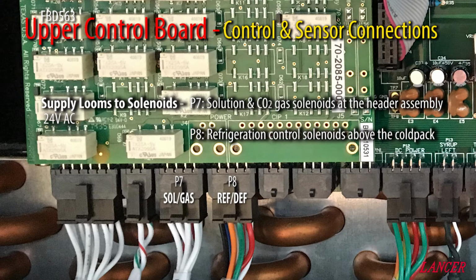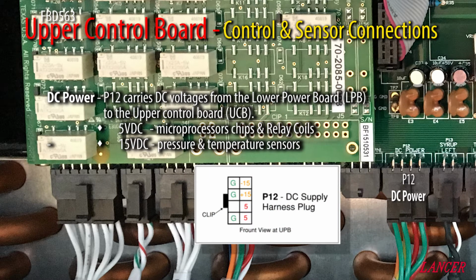These are the output control harnesses. P7 supplies the product, solution and gas solenoids. P8 supplies the refrigeration, pulse and hot gas solenoids. P12 is the DC supply cable from the lower control board. It supplies 5 volts and positive and negative 15 volts DC to the upper control board. There are LEDs and test points to confirm and assist with troubleshooting of these voltages on the upper control board. The pinout of the female plug for P12 is for reference. This may also be required during troubleshooting.